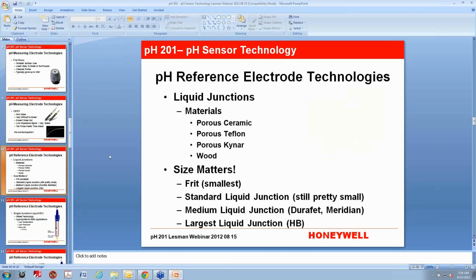Okay. So that's some measuring electrode technologies, and that's important in terms of matching it up with your process, depending on, you know, if your process craps up a lot, if it's thick or a slurry, or if you have particulates, if you need a particularly fast response, and also depending on what your pH range is going to be. The next side is the reference side, and the reference side has a couple of components you want to look at. We want to look at the liquid junctions, and then we want to look at the formulation of the potassium chloride in the reference itself. And that's important because a lot of pH sensors die because the reference gets poisoned. And this is all important in determining if you have the right technology in your process, or if you can tweak it a little bit to get longer life, less cleaning, less calibrations, etc.